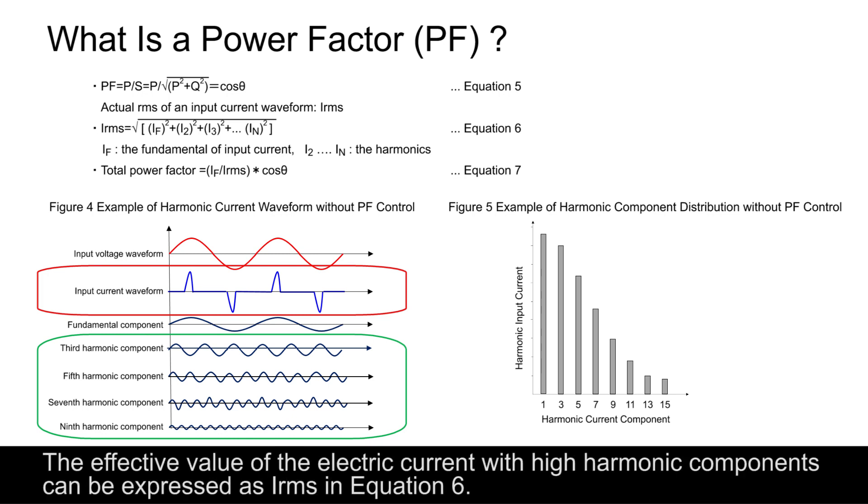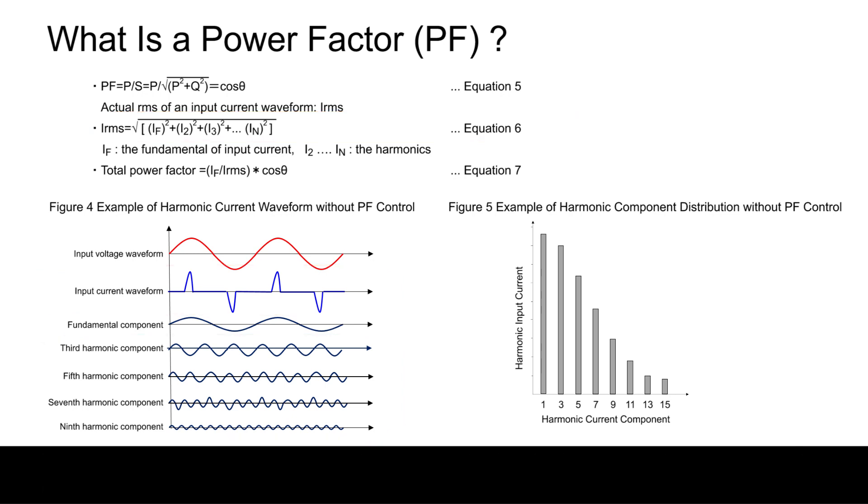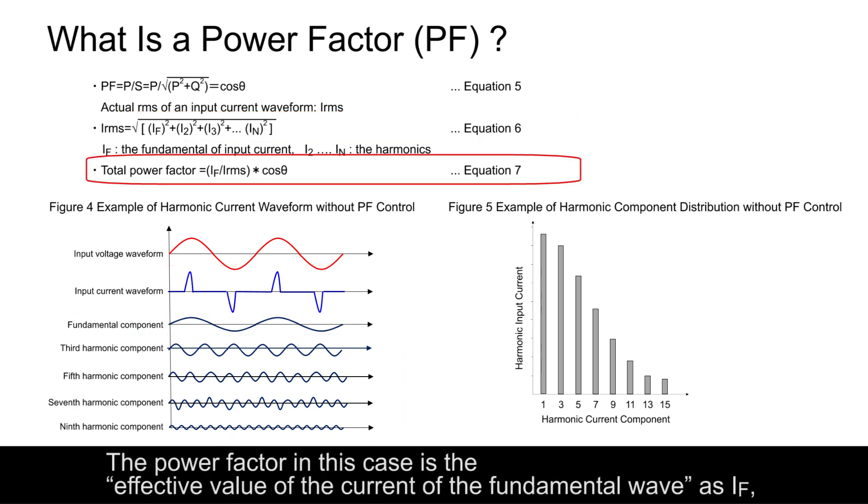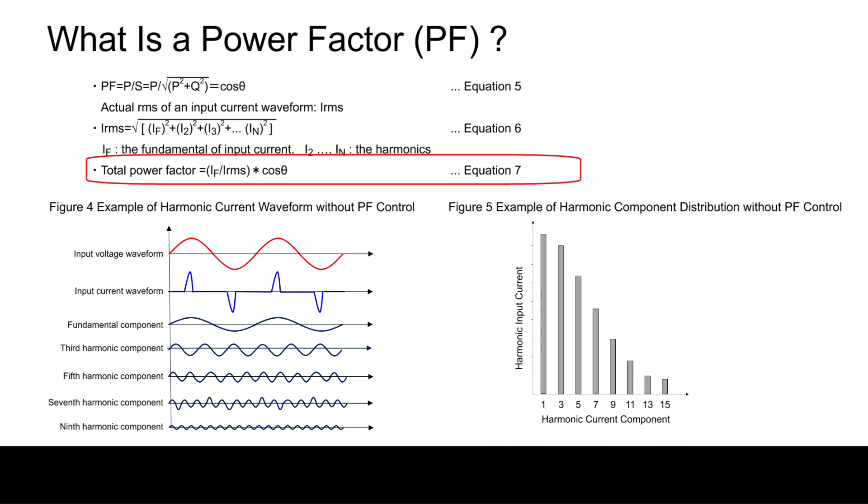The effective value of the electric current with high harmonic components can be expressed as IRMS in equation 6. The power factor in this case is the effective value of the current of the fundamental wave as IF divided by IRMS times the power factor cosine of the fundamental. This is called the total power factor.